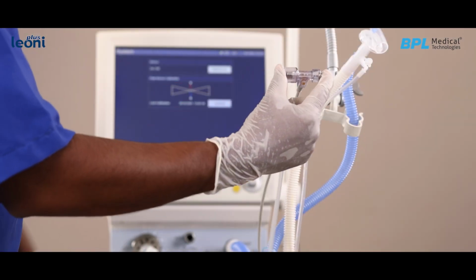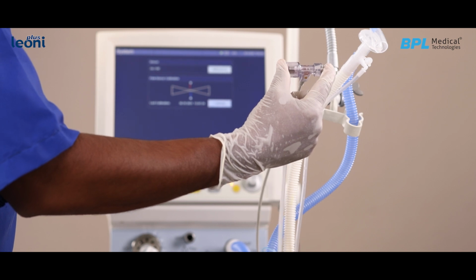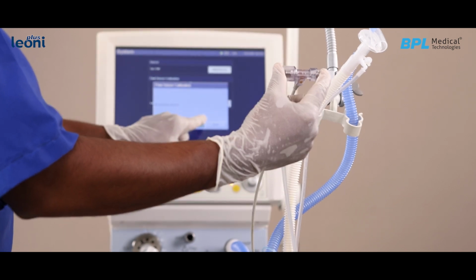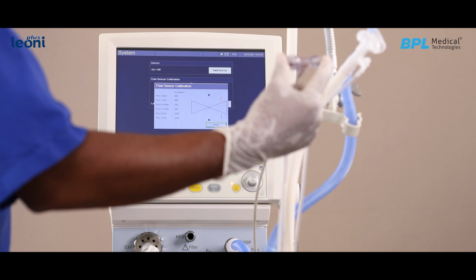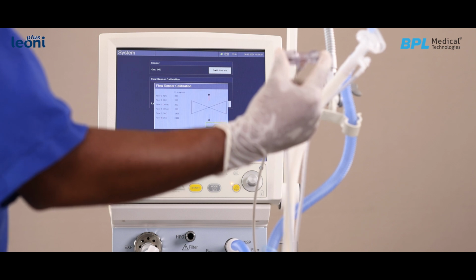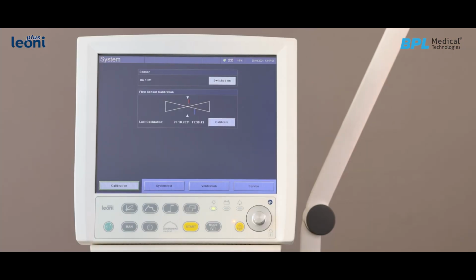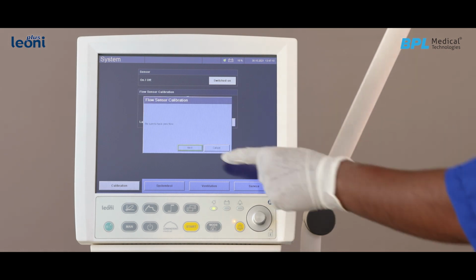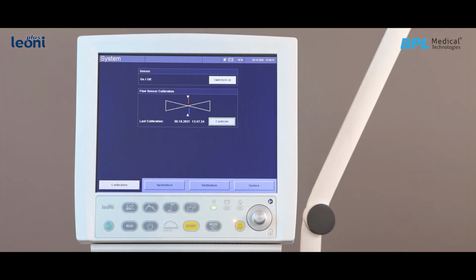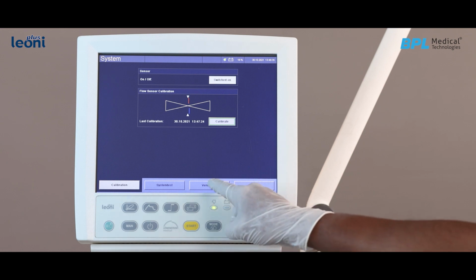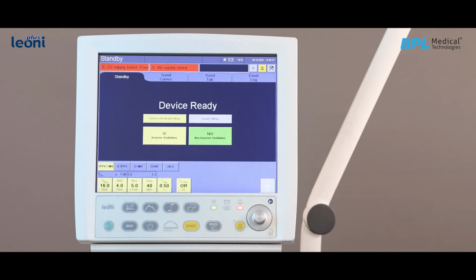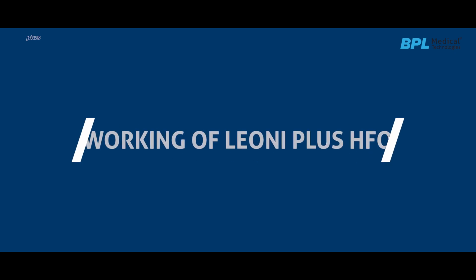Block the expiratory flow sensor with thumb and forefinger. Press Calibrate and then press Next. We can see blue and red line movement with voltage variations. These lines should coincide at the center and give an indication of Done with a beep sound. On completion of successful sensor calibration, press Ventilation at the bottom of the screen to enter the standby mode.